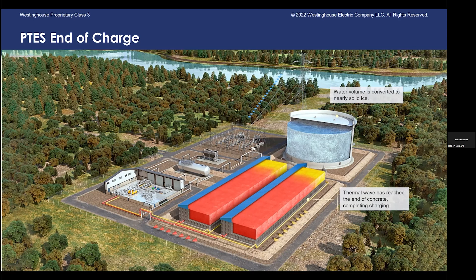With that stored heat, to discharge electricity back onto the grid, we take that heat and let it operate a heat engine cycle, using the same equipment. The difference is we're running an expansion of the CO2 through a turbine versus a compression cycle when charging. We use regular turbo machinery you'd see in any power plant, which has the benefit of rotating inertia connected to the grid, providing ancillary service capability. We can idle the unit when not charging or discharging to provide reactive power support to the grid and overall grid stability.